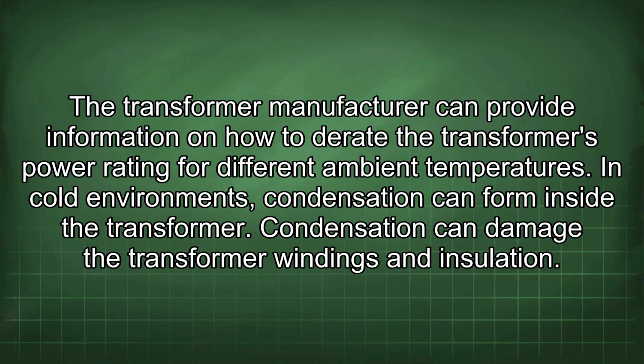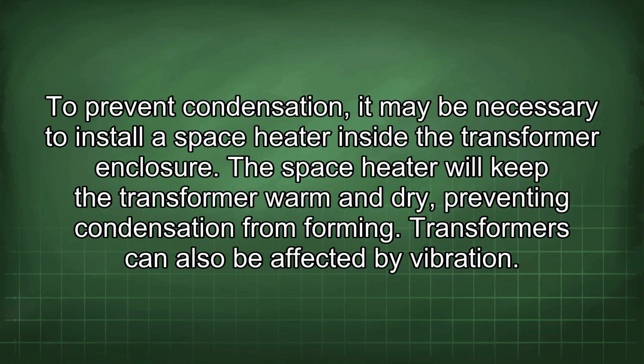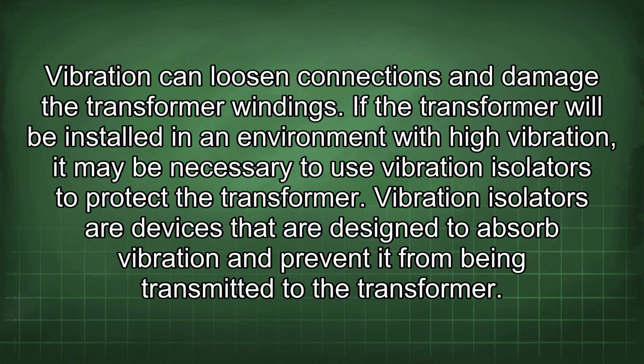In cold environments, condensation can form inside the transformer. Condensation can damage the transformer windings and insulation. To prevent condensation, it may be necessary to install a space heater inside the transformer enclosure. The space heater will keep the transformer warm and dry, preventing condensation from forming. Transformers can also be affected by vibration. Vibration can loosen connections and damage the transformer windings. If the transformer will be installed in an environment with high vibration, it may be necessary to use vibration isolators to protect the transformer.